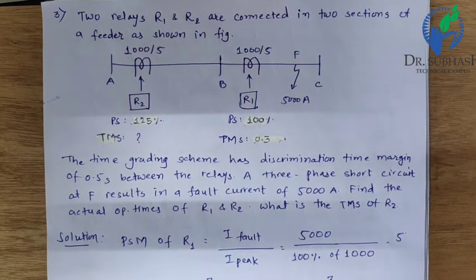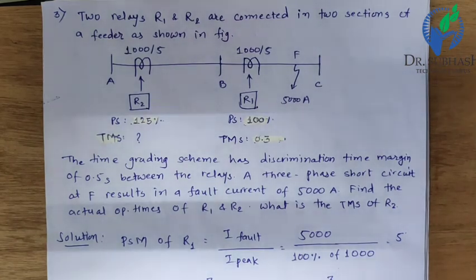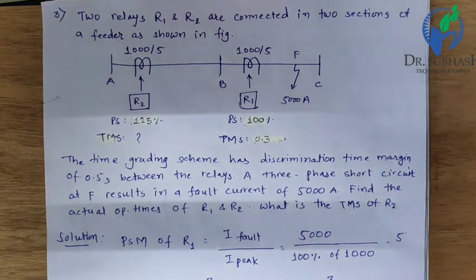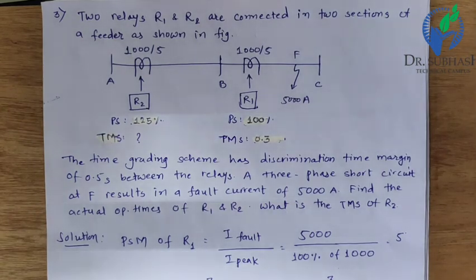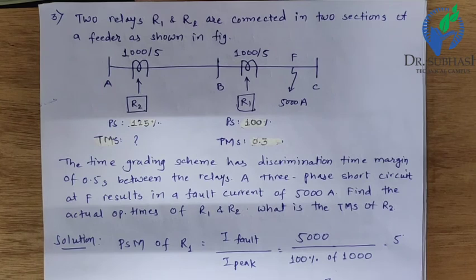Third Numerical: Two relays R1 and R2 are given, with bus bars A, B, and C. Fault current is 5000 A, CT ratings are 1000/5. R1 has plug setting 100% and R2 has plug setting 125%. R1 TMS is 0.3 and we need to find R2 TMS. The time grading scheme has a discrimination time margin of 0.5 seconds. A three-phase short circuit at F results in a fault current of 5000 A.